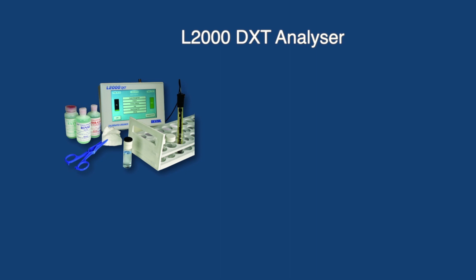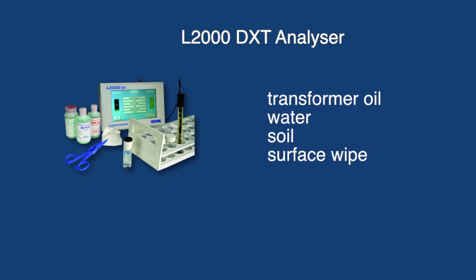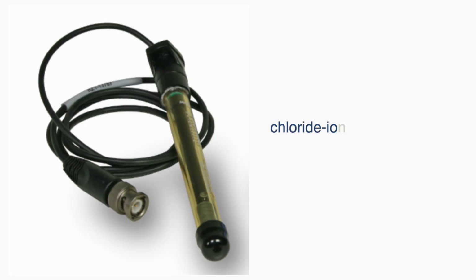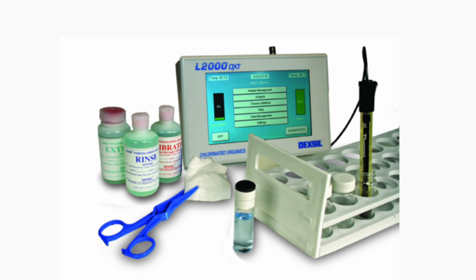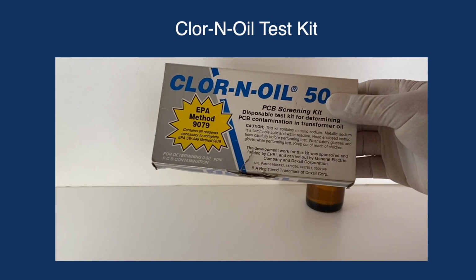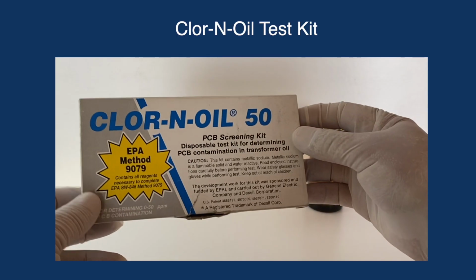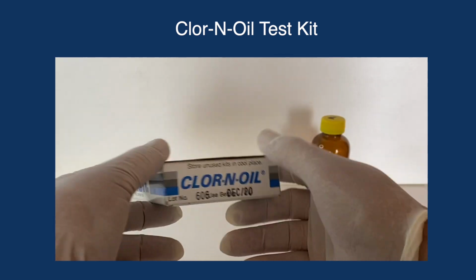The L2000 DXT is a portable analyzer system for on-site analysis of PCB suitable for 4 matrices: transformer oil, water, soil, and surface wipe samples. The chloride is detected and quantified using a chloride ion-specific electrode. The analyzer then mathematically converts the chloride reading to the equivalent concentration of PCB. Conversion programs are available.